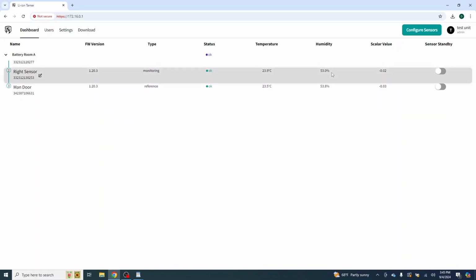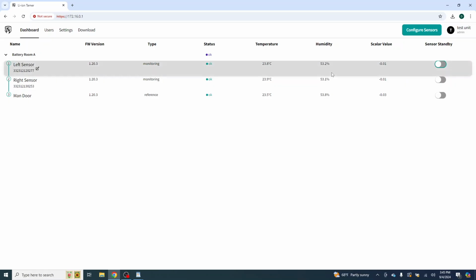And if you look at it from a local application standpoint, it's very simple to design. And right now, I'm going to step over here if I can and grab my VOC that I'm using for testing. And we are going to present to the reference sensor first. So you'll see on the reference sensor that we have an alarm active.